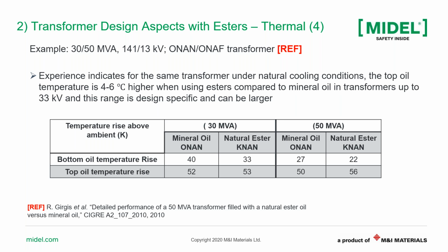Under the 30 MVA, which is the loading, you see mineral oil under ONAN and natural ester under KNAN. So the bottom oil temperature for mineral oil is 40 here, for natural ester is 33. Whereas the top oil temperature for mineral oil is 52, for natural ester is 53. You can see the difference. You have reduced bottom oil temperature and higher top oil temperature. And so the total temperature rise from bottom to top is higher under natural esters compared to mineral oil. In this case, only the top liquid temperature increased, by 1 degree, because it's 30 MVA.